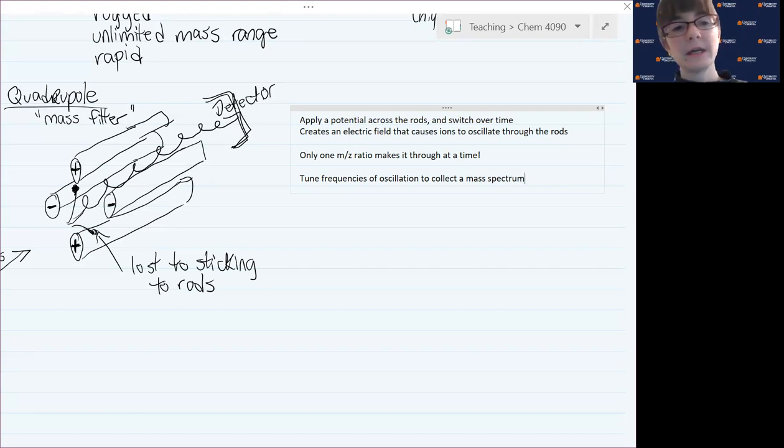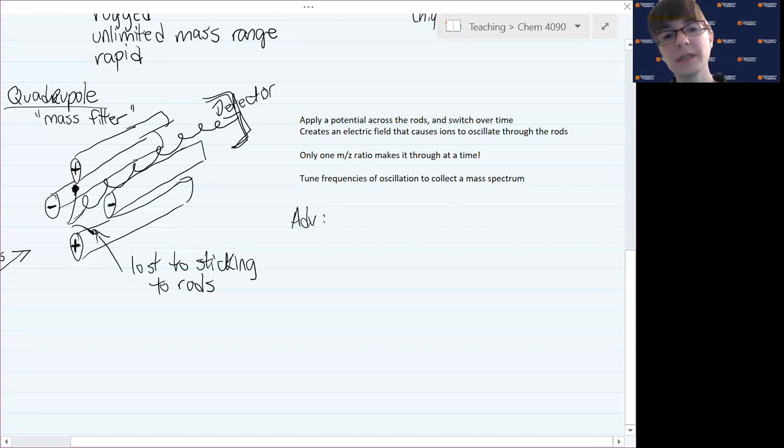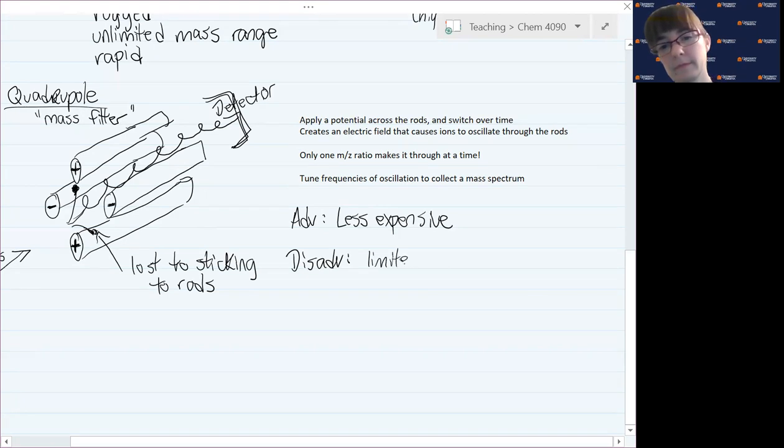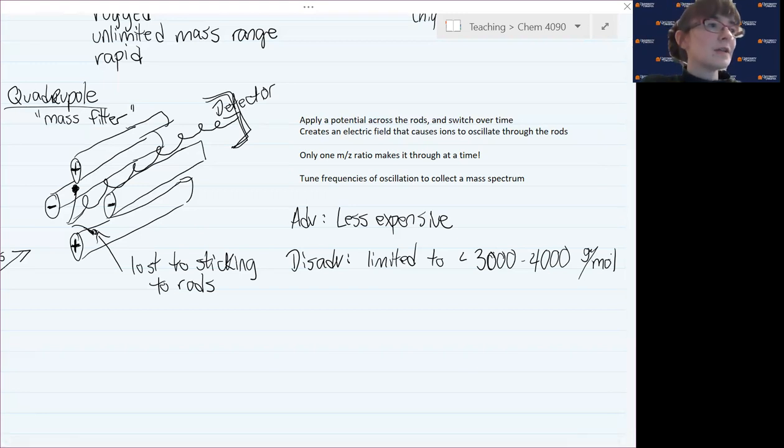That's why we call this a filter because only one m over z molecule makes it through at a time. It turns out, even though this is perhaps more conceptually complicated, it's actually less expensive because it doesn't require as high of a vacuum pull in order to maintain it. But it has some limits on the mass range. About three or maybe 4,000 grams per mole is usually all that we can detect with this. If it's bigger than that, we need to choose a different type of mass analyzer.